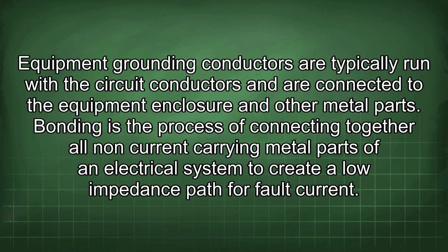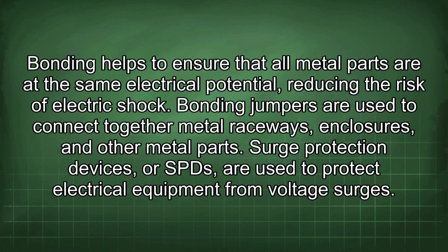Bonding is the process of connecting together all non-current carrying metal parts of an electrical system to create a low impedance path for fault current. Bonding helps to ensure that all metal parts are at the same electrical potential, reducing the risk of electric shock. Bonding jumpers are used to connect together metal raceways, enclosures, and other metal parts.